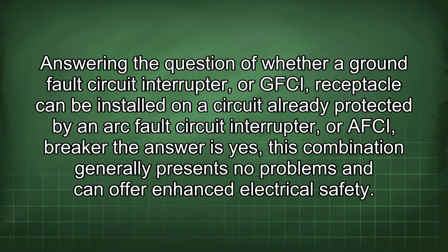This video answers the question of whether a ground fault circuit interrupter, or GFCI, receptacle can be installed on a circuit already protected by an arc fault circuit interrupter, or AFCI breaker. The answer is yes. This combination generally presents no problems and can offer enhanced electrical safety.